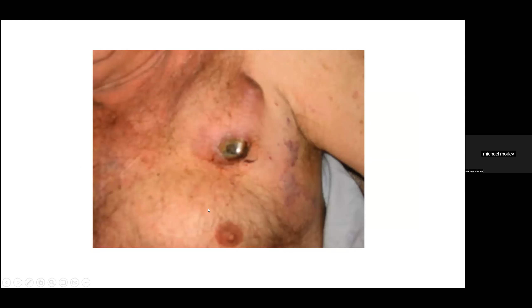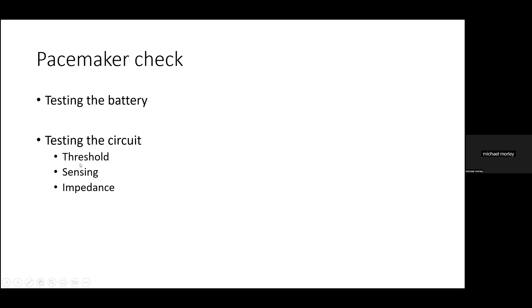This is the pacemaker working, so when they come back to the pacemaker clinic, we'll test to see how much battery is left. We'll test the threshold and the sensitivity and the impedance in the same way that I described with the temporary pacing. And that is the basic pacemaker check that we do every time. There are other things that we can look at at the time of the pacemaker check. We can look and see what rhythm the patient's in or has been in. So if they've had paroxysmal atrial fibrillation, the pacemaker will tell us that and tell us how much. And we can look at other things that we might want to adjust.